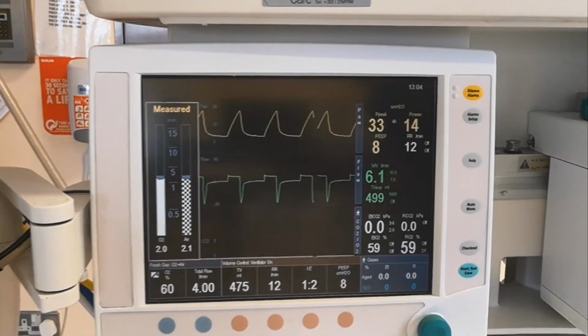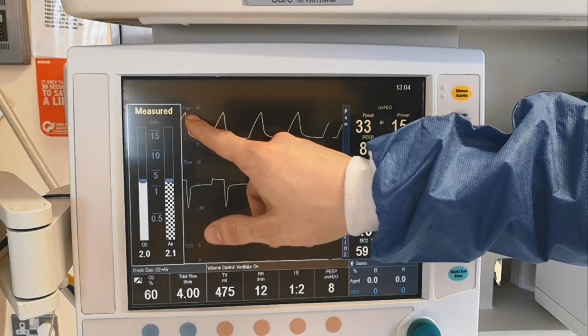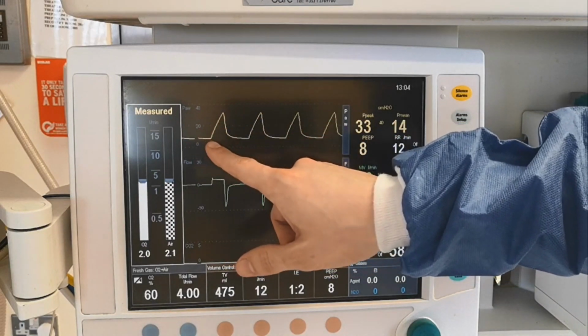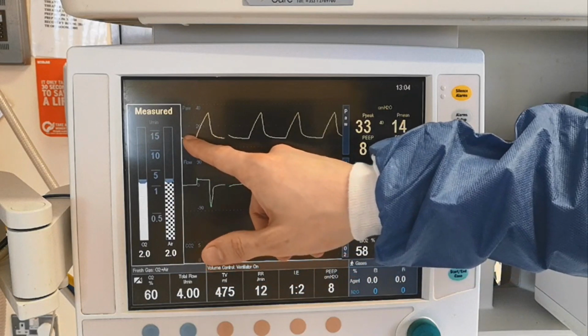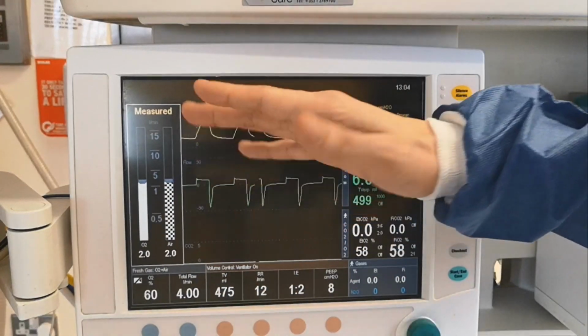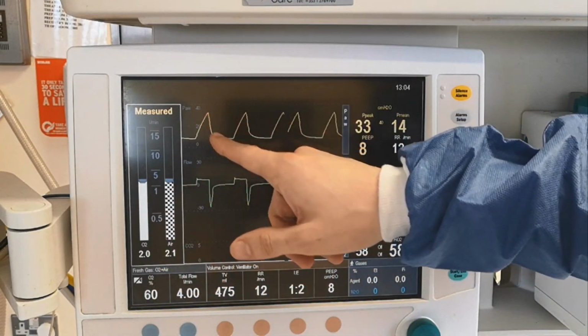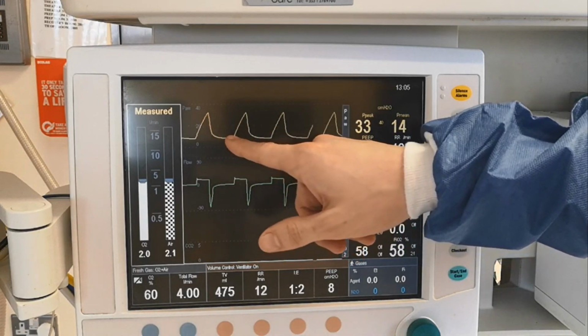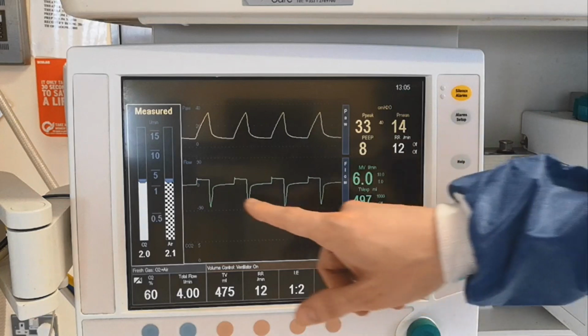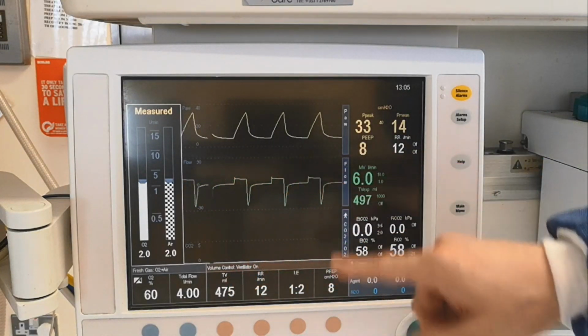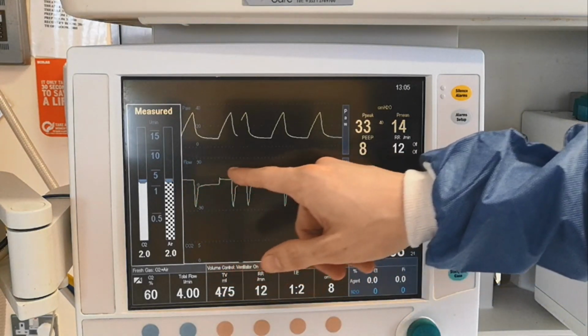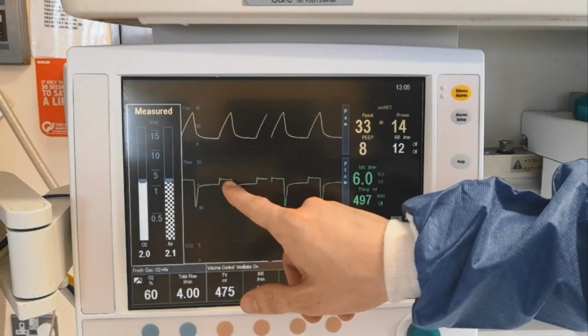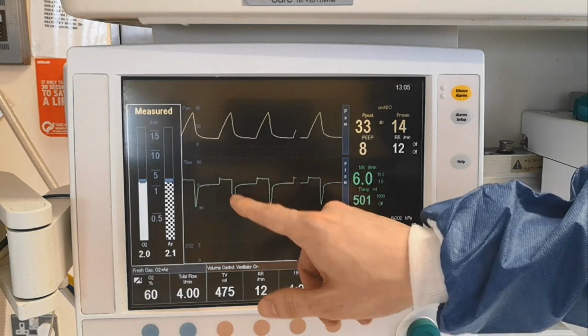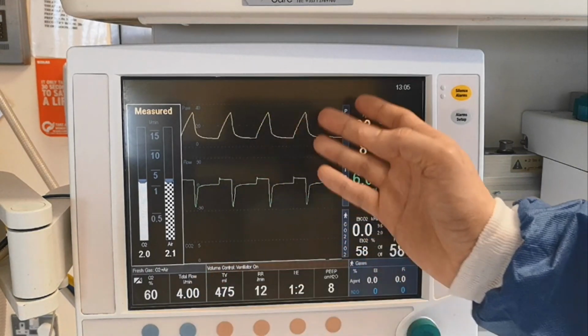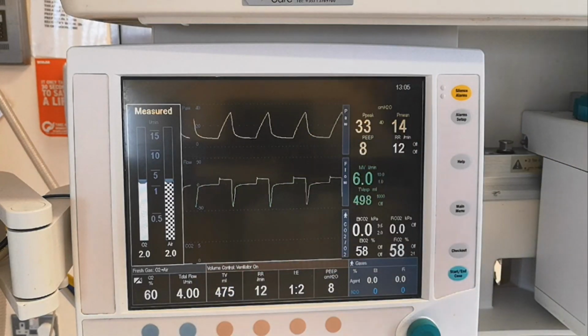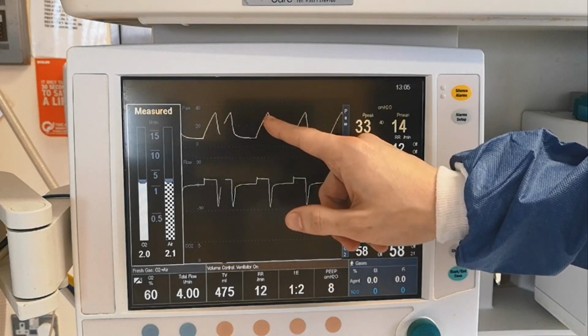The screen here shows a couple of curves. The first one is the pressure curve. As you can imagine, every time we push air into the patient's lungs, we have an increase in the pressure in the airways. And then, of course, when the inspiration phase ends, you have an expiration phase, and then the pressure drops. That's the pressure cycle over time. Here, you have the flow readings. You have positive flow when the air goes into the patient, and then when the air comes back from the patient into the circuit, you have negative flow. It's the direction of the flow. Positive is towards the patient, and negative is towards the machine. So really, this is the pressure curve and the flow curve.